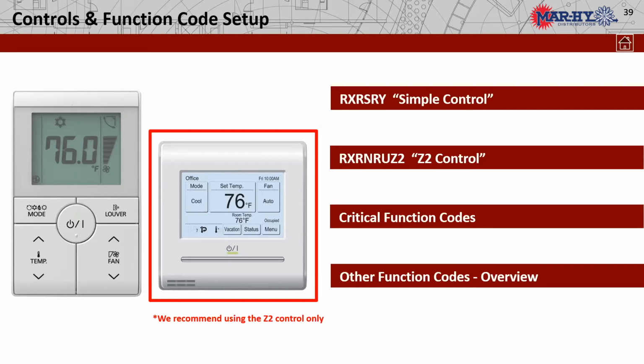Now, these can run as a primary and secondary thermostat on 1 unit. I do have that set up here in the training room, just to see how they function together. So basically you can have the primary and a secondary, and all it does is you can change settings, and it changes in both controllers. I don't know where that might be applicable, but it is something that is available.